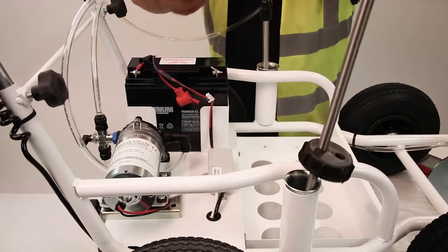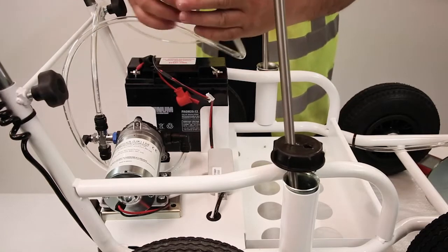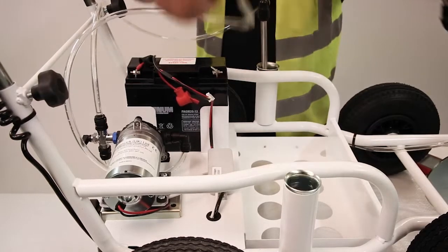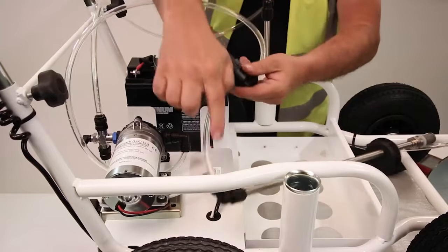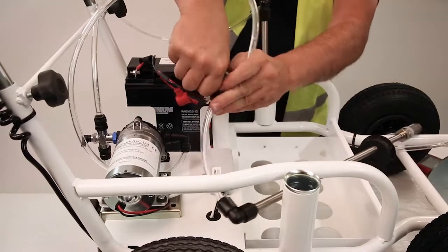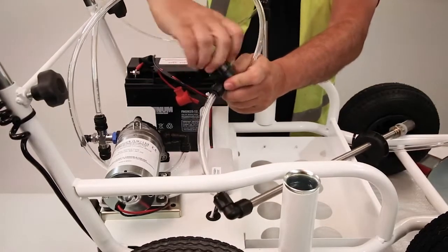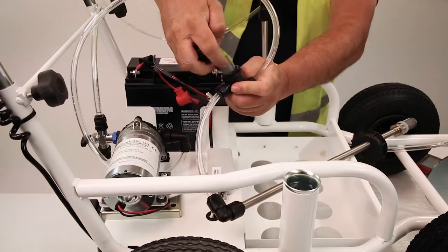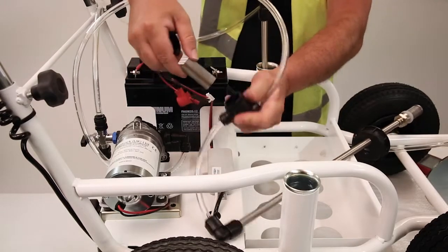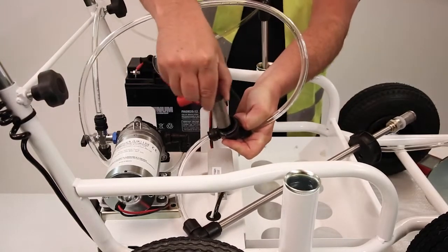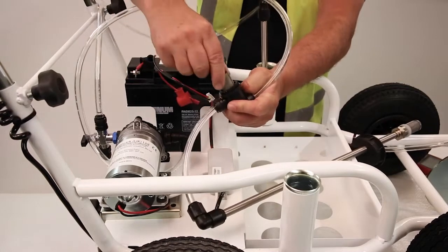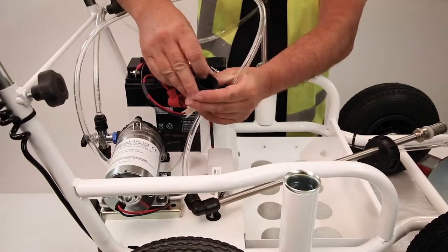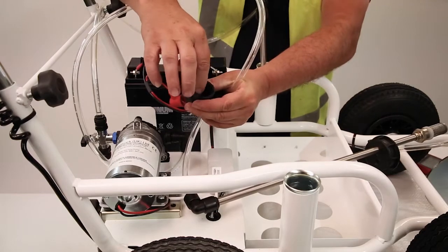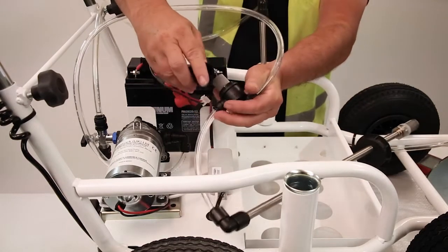Follow that same pipe work through and come to the inline filter, coming off the probe. Take the top off. Inside is a wire mesh filter. Make sure all the inlets and outlets are clear and the filter is clean. Most importantly, inside the filter here is a rubber seal. Must ensure that the rubber seal is there.